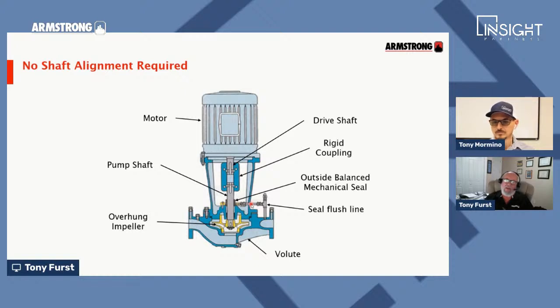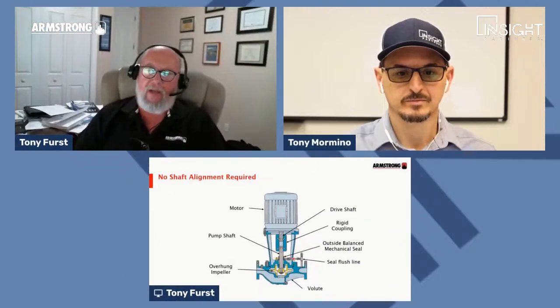Okay. If I have a base mounted end suction pump with a back pull out, I've got to take the coupling apart. There's a whole bunch of bolts I've got to take out to pull the impeller and bearing assembly out. I've got to put it on a bench. I've got to take everything and disassemble everything to rebuild it and put a new shaft seal in, probably new bearings, put it all back together again. Now put the pump back together. I've taken a whole lot of time to do that. With this, I'm in less than 30 minutes.